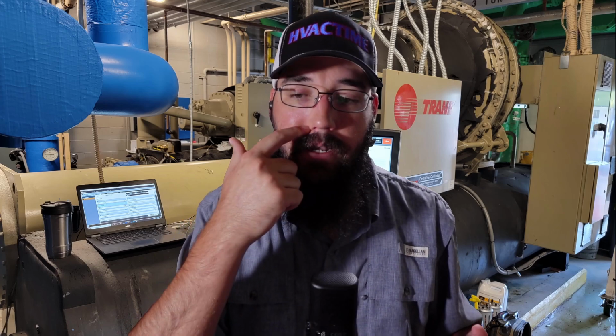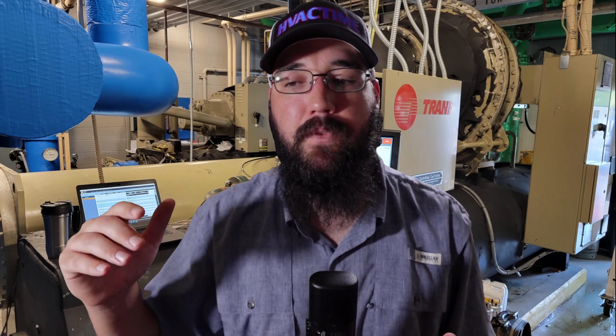That's a typical symptom. And what that means is that the valve is mechanically in an early stage of failure, and that its position is not controlling correctly as it is able to operate. As the refrigerant force and everything else that's happening against it, it's losing that calibration. And so, even though the machine thinks it's at 100% valve position, it's really only at 50%. And it just doesn't have any other way to know that.